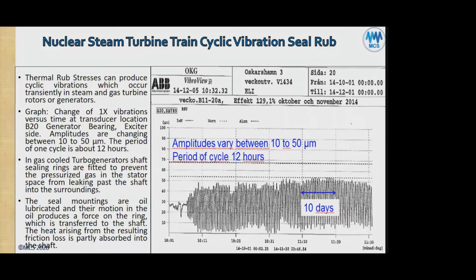Now, if we ask why a periodic cycle of 12 hours, it means there must be something else involved. So they didn't mention this, but to get a cycle of 12 hours means that, number one, it could be due to night and day thermal growth of the foundations of the machine. Okay, they would push the generator bearings up or down slightly and cause a change in the alignment of the seal to the shaft. And that small change could cause the rubbing. So that's why we see a change every 12 hours, which would be night and day. That's one possibility, and it's probably the most likely possibility.